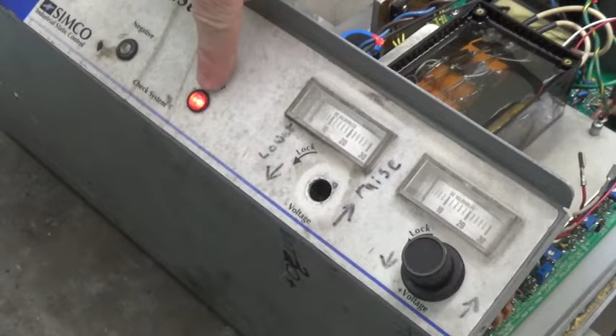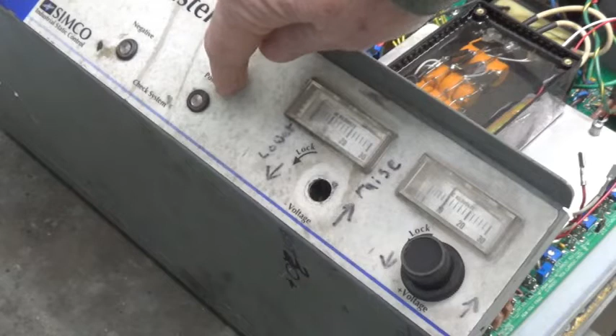Okay. Let's come around to the front of the Charge Master. I'm going to turn it off. Let's come around to the front of the Charge Master. And I'm going to turn it on. Here's the positive check system LED. Notice that it's on right now. Our meter on the positive side is at 0, and we're going to increase that voltage output to 10 kilovolts. There we're at 10 kilovolts on the meter. Notice our LED went out. If we had a problem, that LED would turn back on and the meter would drop to 0. Self-protection.